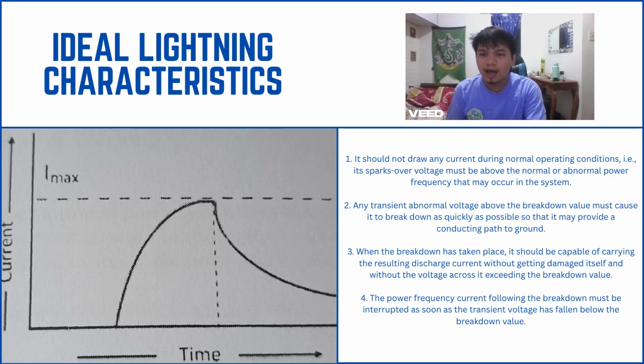Number three, ability to carry discharge current safely. Once the arrestor conducts, it must be strong enough to handle the surge current without being damaged. And number four, fast recovery after the surge. After the surge is over, the arrestor should stop conducting right away. In summary, an ideal lightning arrestor should remain inactive during normal operation.